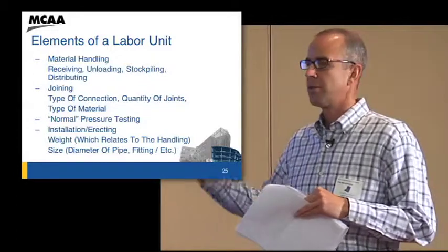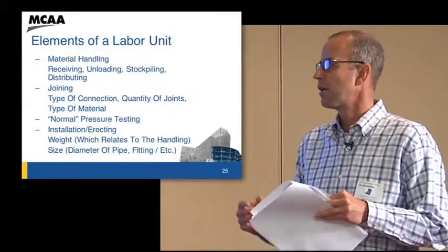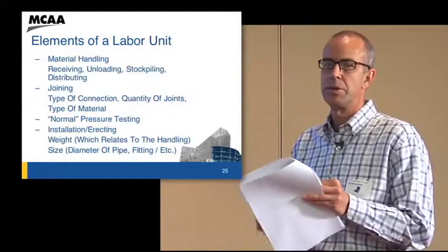When we say material handling, that doesn't mean you can be a mile away and the labor unit accounts for that. It's based on the material moving no more than 200 feet. Like Tim was saying, it does say 200 feet, but sometimes that's not realistic. So it depends on the way your company operates, where you normally have your stockpile of material, and that's going to be part of your productivity factor, if you will. Just recognize that if the laydown area is a long way away, you're going to have to make some type of correction for that, right?